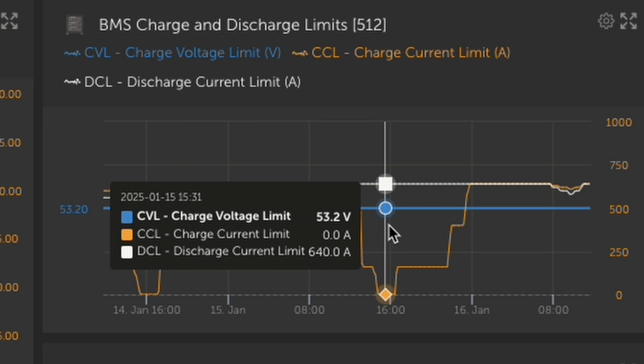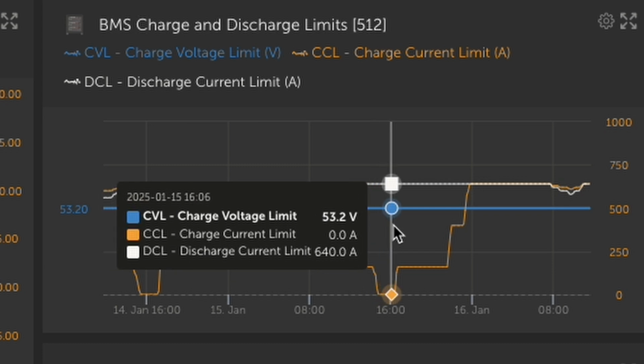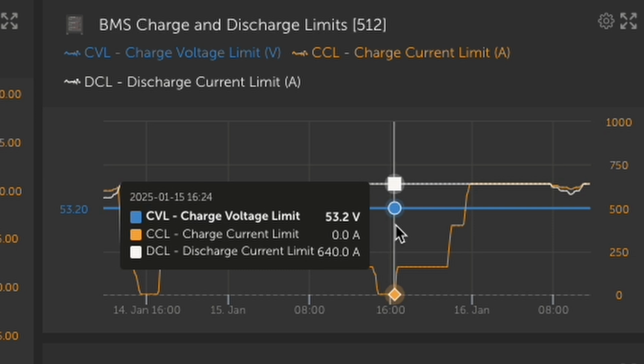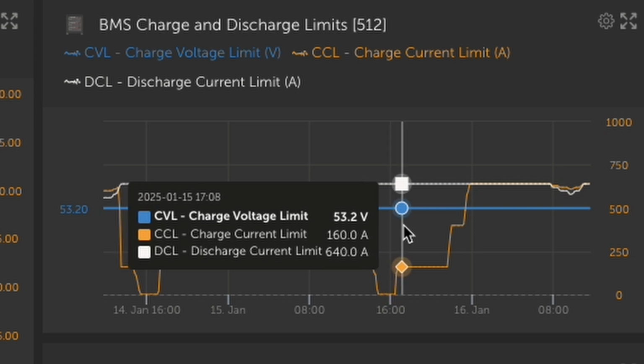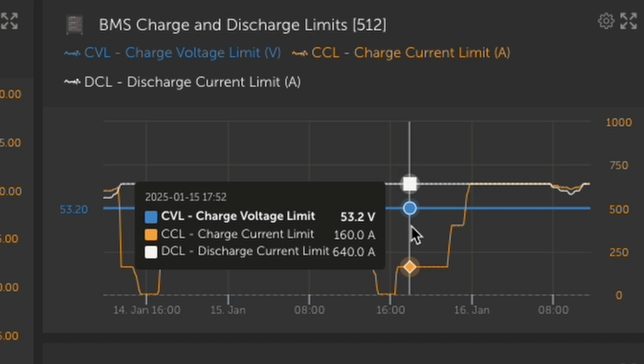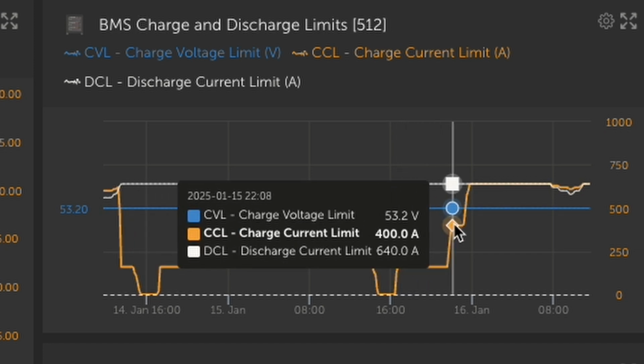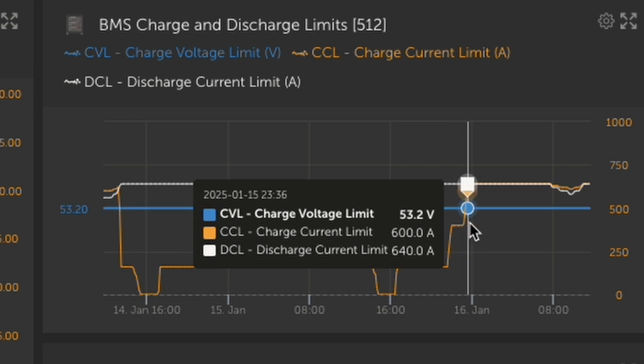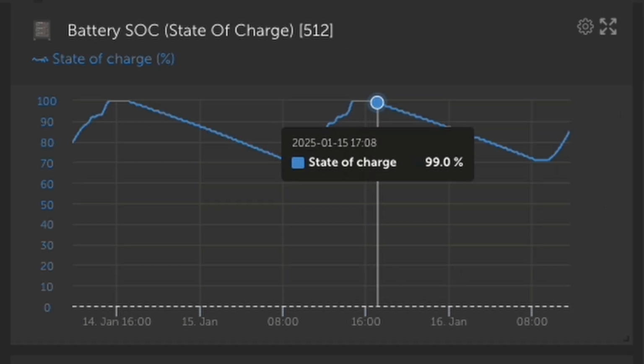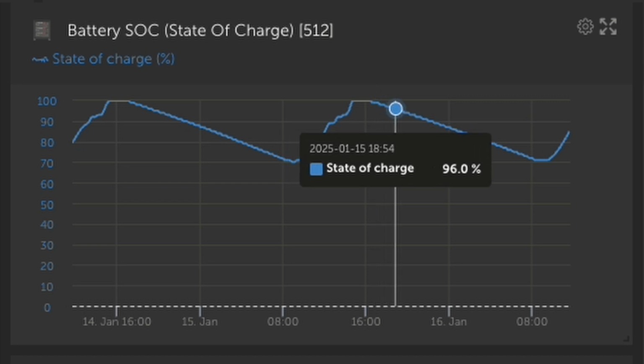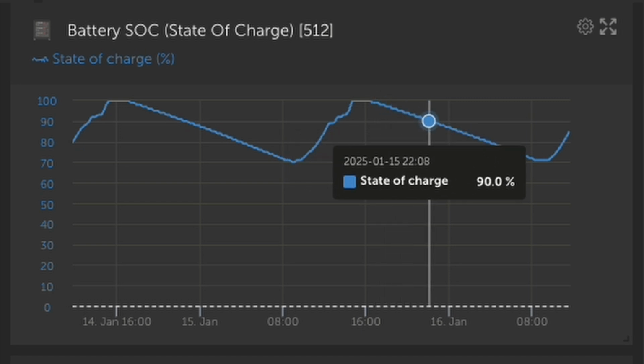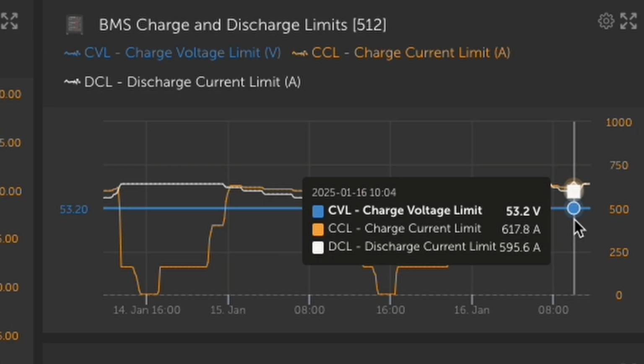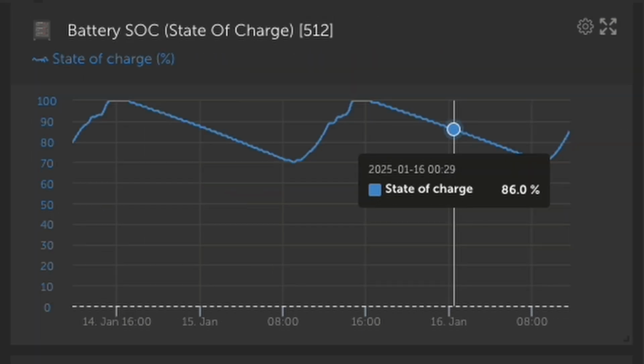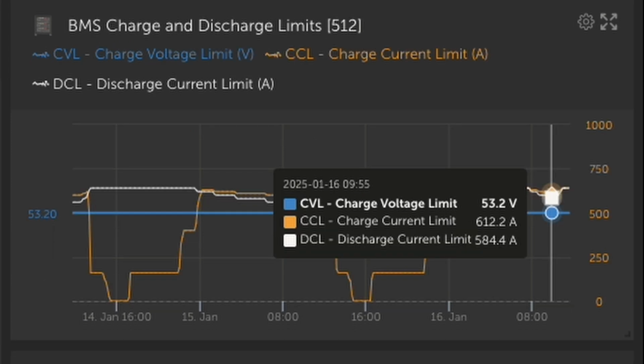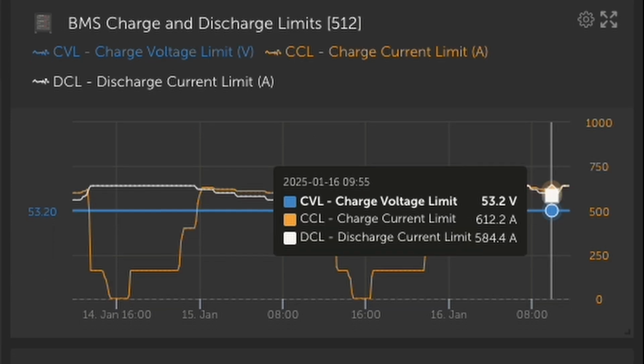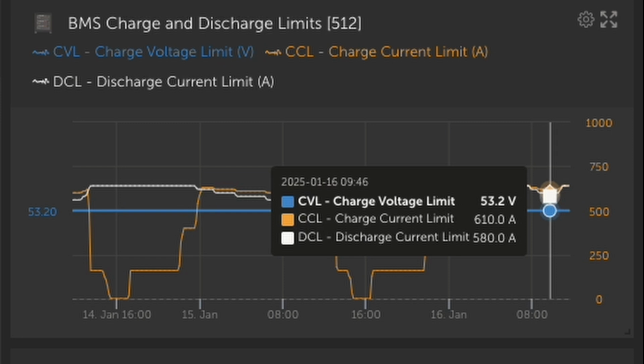In the Victron system, if you have a load on this, and say you've got a 1,000-watt load and at least 1,000 watts of solar available, the system will still be using that solar to power your loads. It's just limiting it so that it makes sure it doesn't overcharge this battery and damage anything. Now, as we drop off throughout the afternoon and start drifting from charging into discharging, and hit 90%, you'll see that charge current limit comes back up. And then as it drops below 90% again, the charge current jumps further, all the way up until we're around 85 to 87%, and we have a wide open charge.